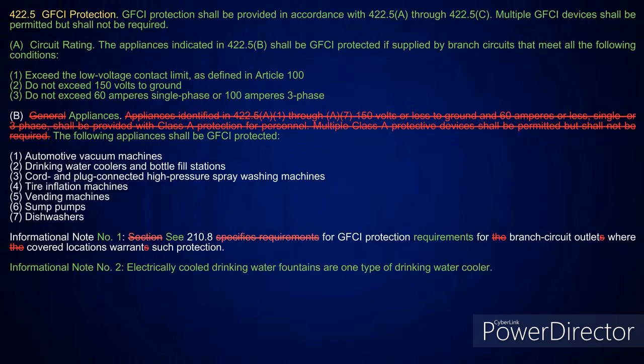For the clothes dryer, if they do that, I think there needs to be a reference over in 250.142(A) and (B) for the GFCI protection, because it comes to be part of the grounding, whether it's a three wire or four wire. That's a really good point, because that gets lost a lot, that a lot of these appliances that become energized don't have a grounded conductor.